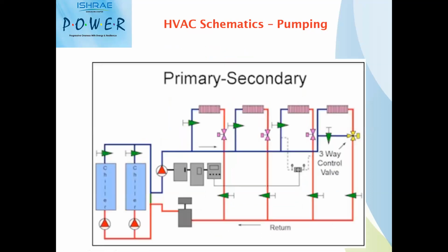Next one is where you have primary and secondary pumps, where the primary pumps are designed for catering the water from chillers up to the secondary pumps, and then the secondary pump will take care of distribution of water to your AHUs or load side based on your application, either 3-way or 2-way valves. And then again, the water will flow back to your primary pumps. Of course, there is a condenser pump if it is a water-cooled chiller, or no condenser pump if it is an air-cooled chiller. So this particular scheme will have one more additional set of pumps, which are called secondary pumps.